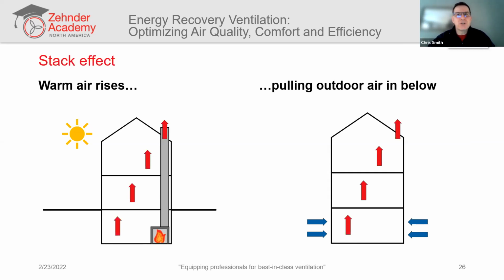This will depressurize the building, and by depressurizing the building, it creates a vacuum, so to speak, in the lower levels of the building. And so cooler outdoor air is pulled in through the lower levels of the building as the building operates like a stack or a chimney.